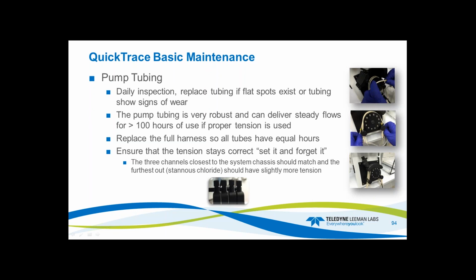Ensure that the tension stays correct. And I always tell people, set it and forget it. Don't adjust pump tubing or pump tension for tubing that's going bad. You're just asking for problems. So leave it as is, change the pump tubing. So all three channels closest to the system should match because we use the same pump tubing, and the diameter of the stannous is a little bit less, so then we use less tubing there.